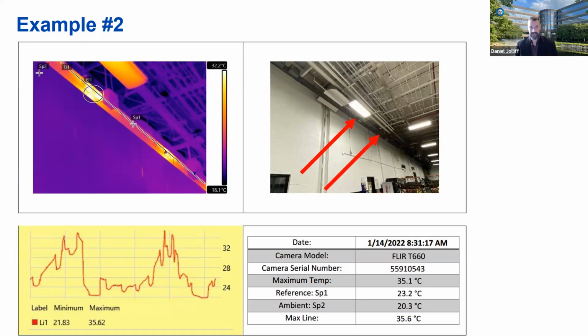So for busways, what we would like to see is a nice and even temperature all the way across the busway, especially because this is high voltage that we're talking about. And as you can see on the thermal image on the left, we have quite a bit of temperature variation inside of the bus duct. This implies that we've got inefficient connections again. It could be dirty, it could be full of contaminants.